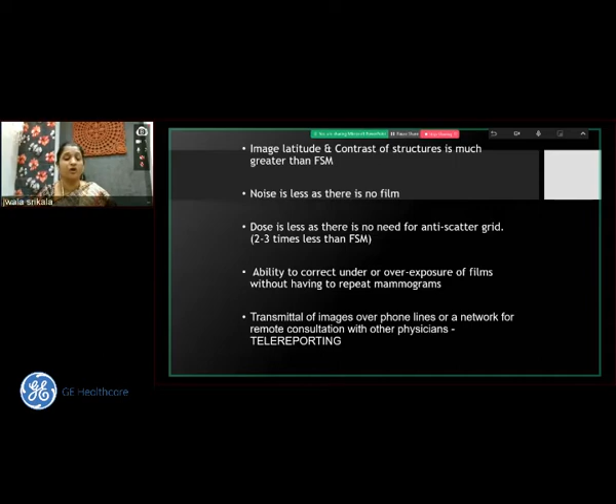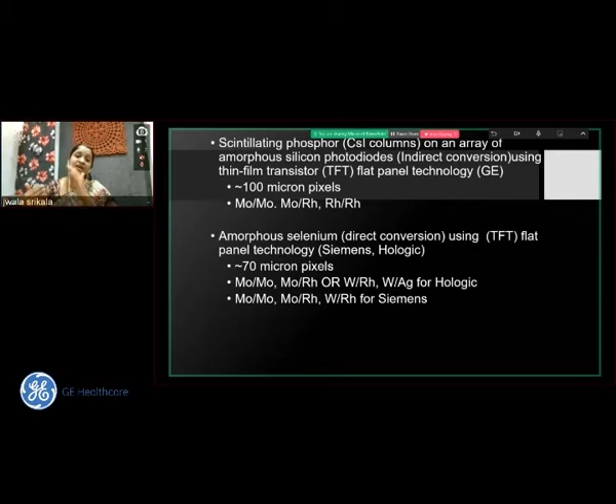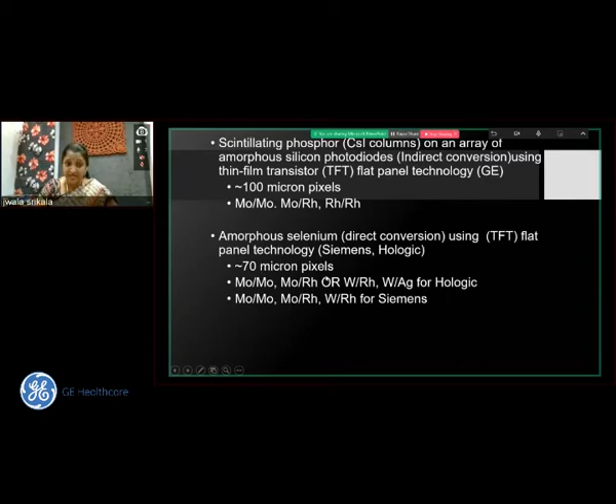So what made it possible? The new detector technology made it possible for us to do digital imaging. These detectors were possible by the use of two to three materials. One was the scintillating phosphor, which is cesium iodide columns on an array of amorphous silicon photodiodes, and a thin TFT flat panel technology. GE was a pioneer in manufacturing the first digital detectors, and it used this indirect method of conversion of the X-rays into light and light into digital information. A little later on, amorphous selenium, which would convert the X-rays directly into digital information, on the flat panels was manufactured, and the resolution was much better with 70 micron pixel size.